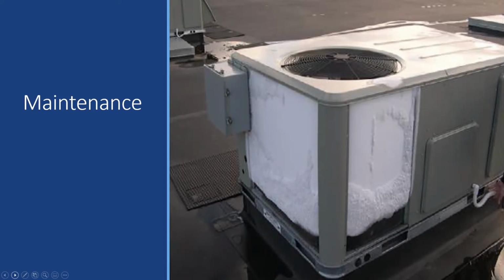Things you want to keep an eye on are whether or not your equipment sounds good. What is a good day versus a bad day? Like your car, you'll need to know when you get things checked out. Oil leaks or drips, and the coil condition. Are the fins dirty? If the fins are dirty, this will lower your efficiency output.